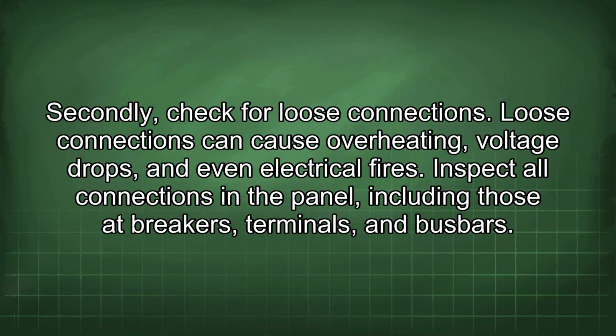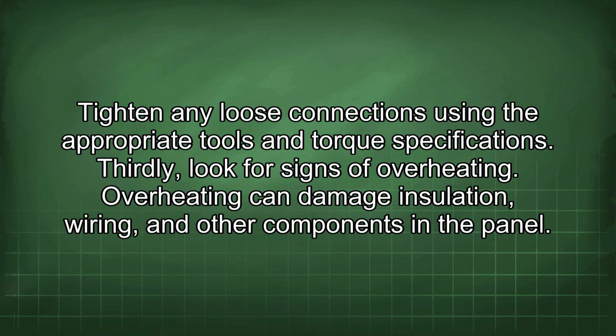Secondly, check for loose connections. Loose connections can cause overheating, voltage drops, and even electrical fires. Inspect all connections in the panel, including those at breakers, terminals, and busbars. Tighten any loose connections using the appropriate tools and torque specifications.